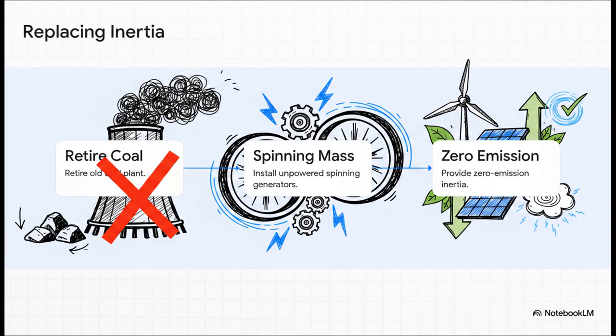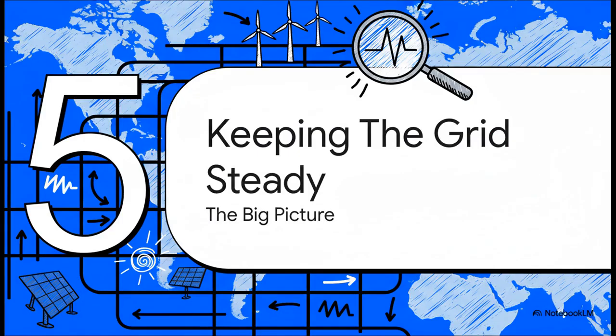And there's a truly fascinating real-world example of this arsenal in action right now. Over in the UK, they retired the massive Fiddler's Ferry coal plant, which completely removed its physical inertia from the grid. To fix that weak spot, engineers at the Lister Drive project in Liverpool installed massive synchronous condensers. They basically installed the huge spinning heavy machinery of a power plant, but attached a motor to spin it, using grid power instead of burning coal. The result? Within just 15 minutes of getting a command, this one facility provides 1% of the total inertia needed to safely operate the entire British grid, with absolutely zero emissions. How cool is that? We are literally rewriting the rules of how electricity is managed on a continental scale.